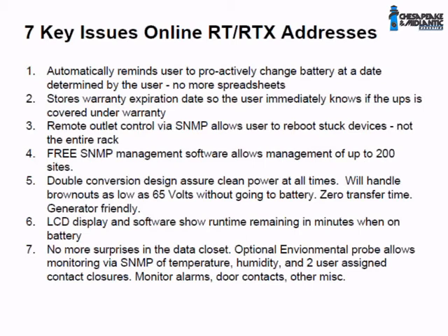This unit has an optional environmental probe that monitors temperature and humidity, and also allows 2 contact closures to be assigned to it. So if you want to know every time a door opens, or anytime someone opens the rack enclosure, you can set an SNMP trap to tell you every time. You can assign those 2 contacts to anything you want.